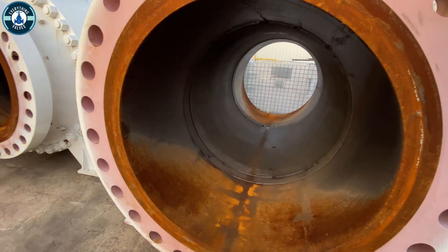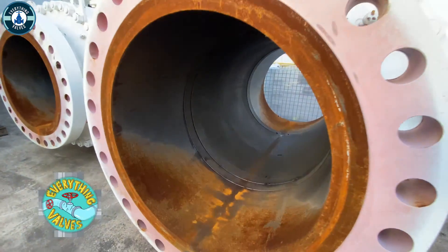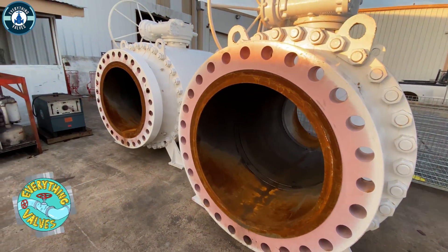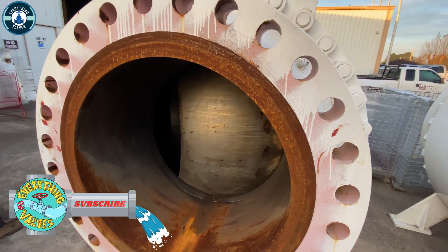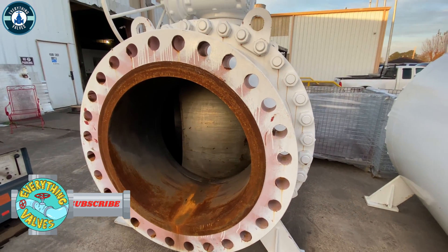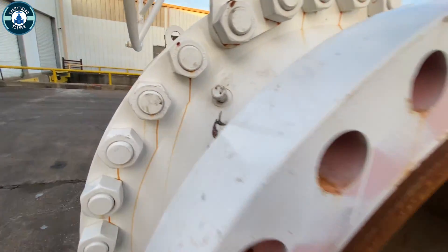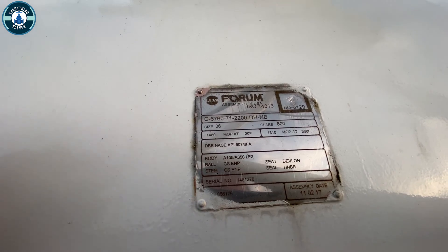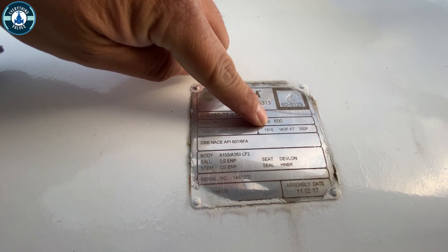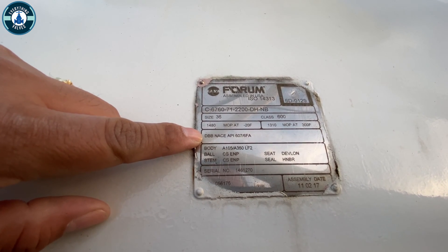This is going to be a Forum PBV 36-inch class 600. The MOP, or max operating pressure, at minus 20 degrees is going to be 1480 PSI. Over here is the maximum operating pressure at 300 degrees Fahrenheit, and that goes down to 1310 PSI.